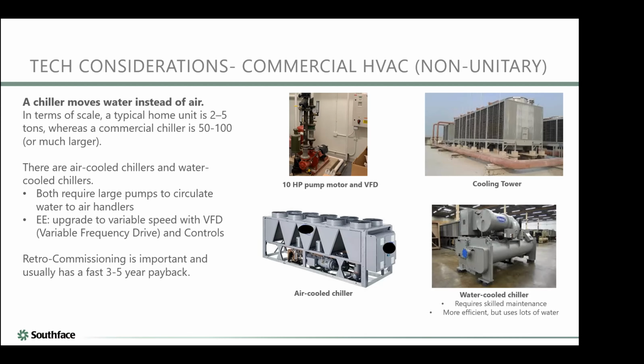You can invest in a more efficient chiller, and they also have water-cooled chillers that are more efficient than others. Water-cooled chillers tend to require more skilled maintenance and upkeep than air-cooled chillers, but they're more efficient. Water-cooled systems use a lot of water, and you need that cooling tower, shown in the top right picture, on the outside of your building to evaporate the water and work with the chiller.